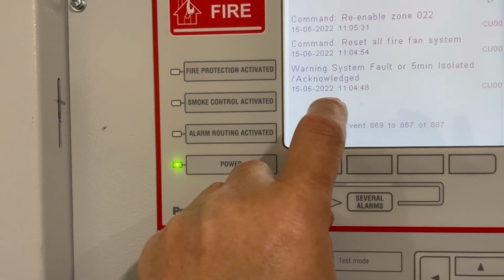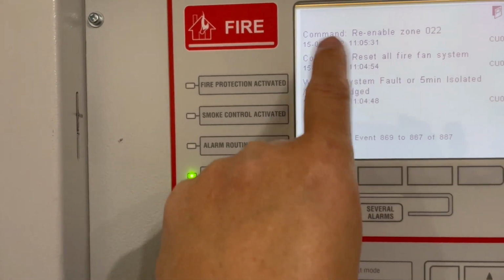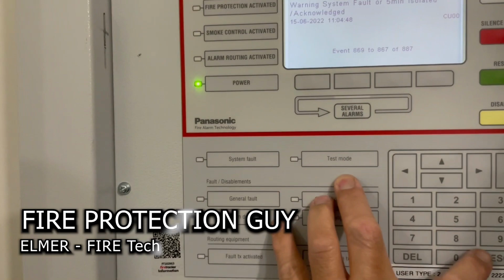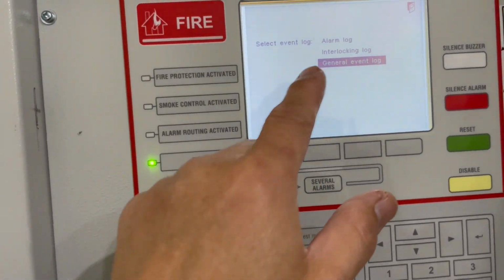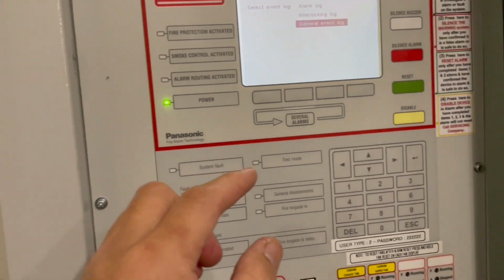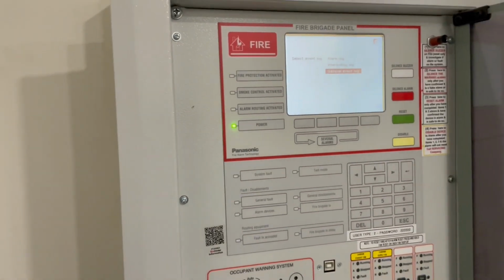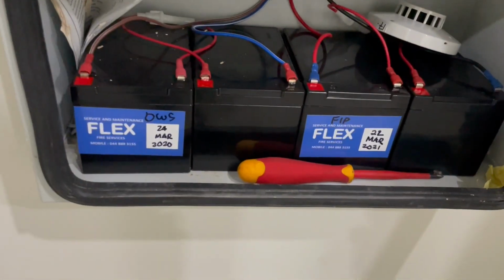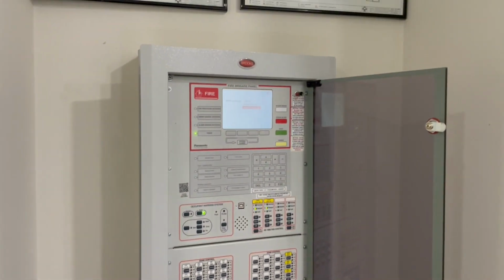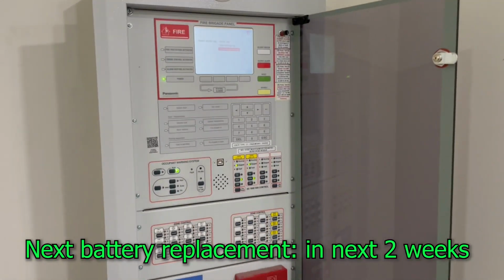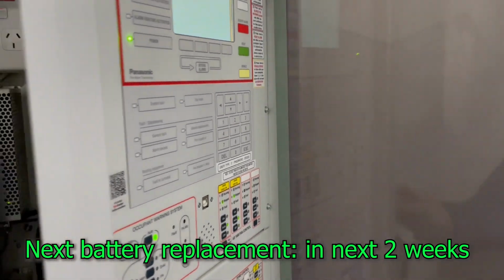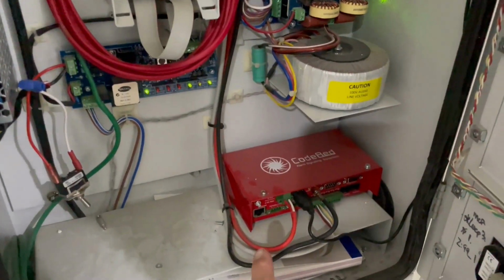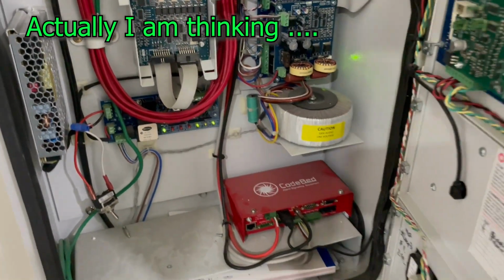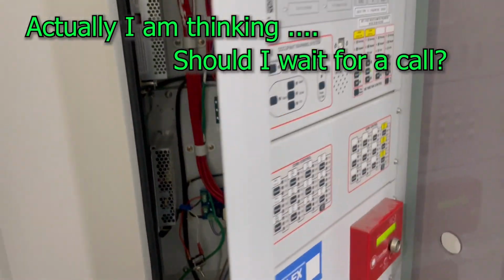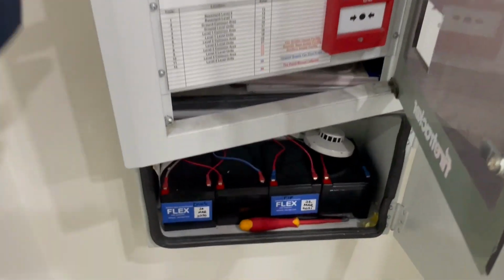Okay. Warning system acknowledged fault. No, that was when I was doing my testing, so it's nothing to do with it. So therefore, it's happening at night. The system is testing itself at night, and it looks like we need to change that battery. So I'll be back to do that in my next monthly test. But for the meantime, I'm going to wait for Code Red to give me a call if another fault comes up. And then when I attend next time, I'll bring the needed battery.